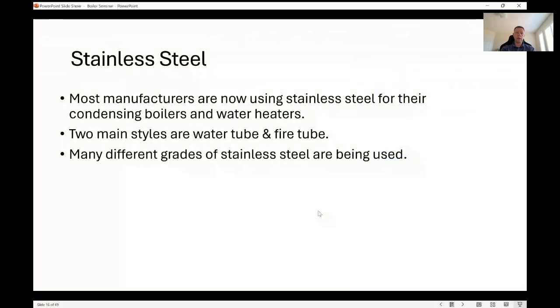I think stainless steel is probably the most common one these days. Most manufacturers, I believe, have a stainless steel product out there. There's two main types: water tube and fire tube. They have different properties, and you have to apply them a little bit different. And of course, there's a lot of different grades of stainless out there. I think 316L is a very popular grade, or 316 Ti. You see a lot of those. And that's what's called an austenitic grade of stainless steel. They tend to be high in nickel, which is good. There's also 439, which is popular out there. It's a ferritic grade. And then there's some people using various duplexes. A duplex is a grade where they take a ferritic and an austenitic and blend them together. But that's a whole other presentation.